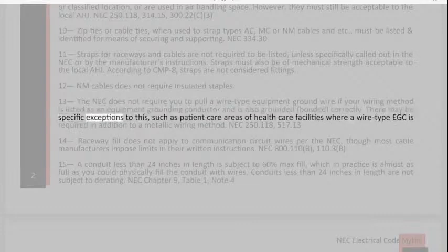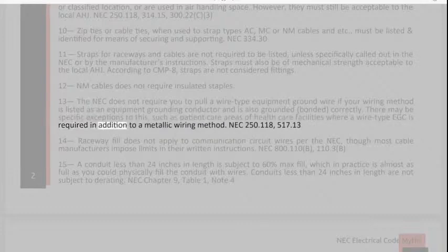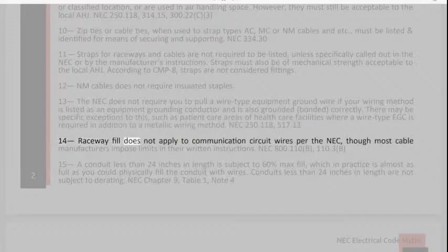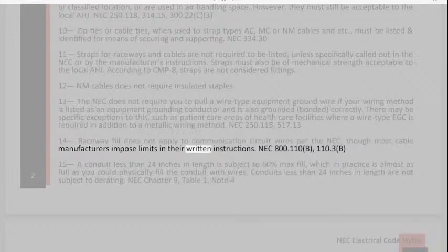There may be specific exceptions to this, such as patient care areas of healthcare facilities where a wire-type EGC is required in addition to a metallic wiring method. NEC 250.118, 517.13. 14. Raceway fill does not apply to communication circuit wires per the NEC, though most cable manufacturers impose limits in their written instructions. NEC 800.110b, 110.3b.